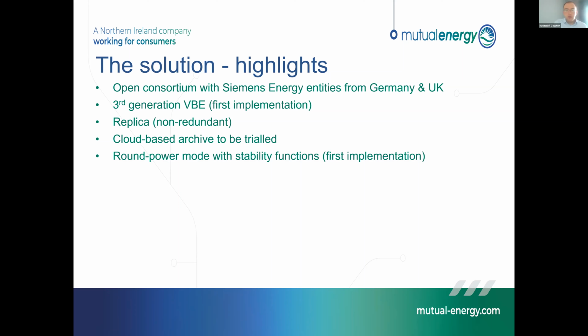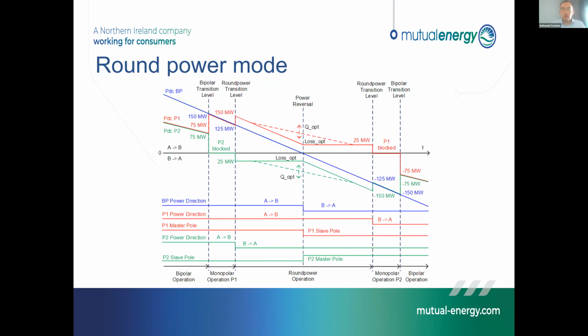And then the round power mode, this is to address Moyle's deadband issues that Sam mentioned. Currently the LCC converter doesn't operate between 0 and 15 megawatts. So what this does is it allows power flows in that deadband of -15 to +15 megawatts, basically by transferring power in opposite directions in each of Moyle's 2 poles, and then the total power that Moyle provides is the net of those 2. So, for example, if you wanted to have 10 megawatts, you could put 50 megawatts in one direction and 40 megawatts in the other direction, and your net transfer would be 10 megawatts.